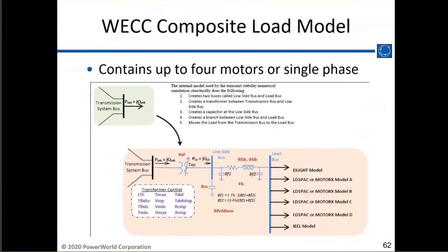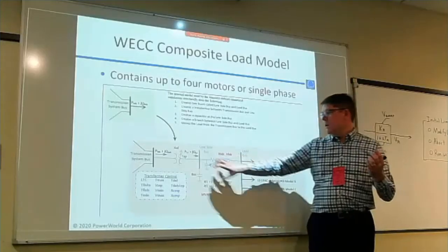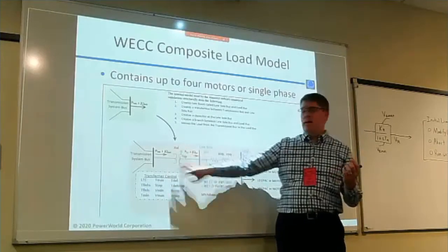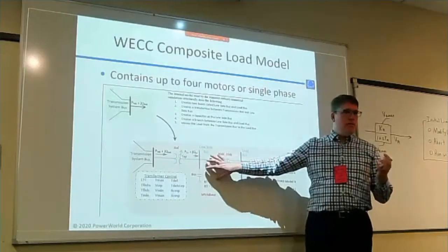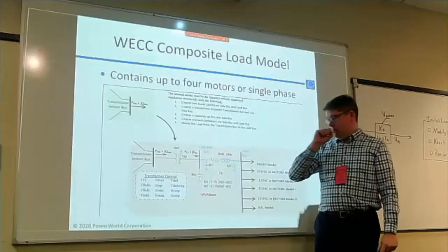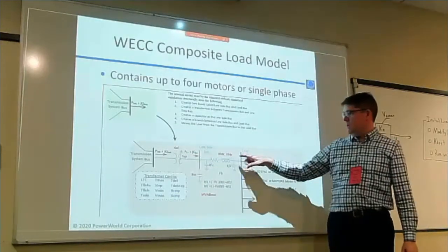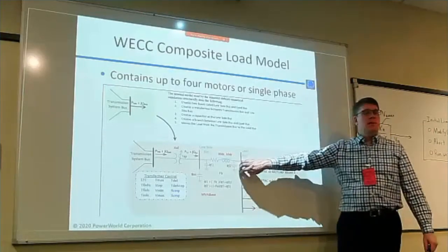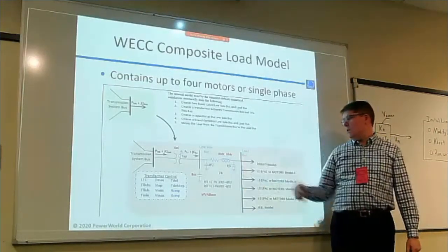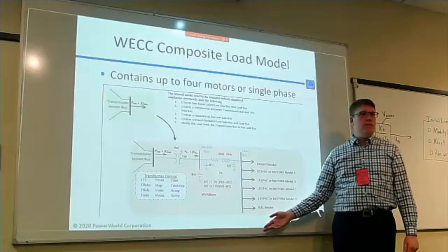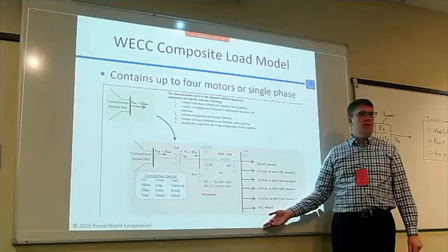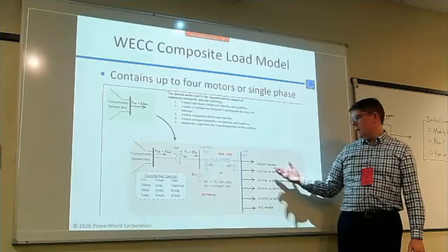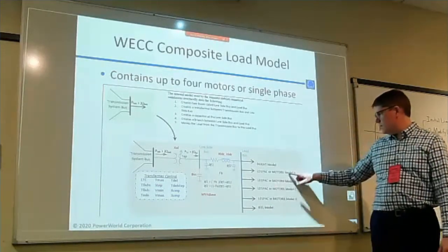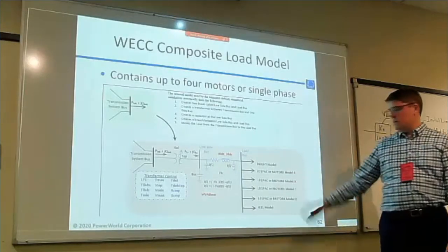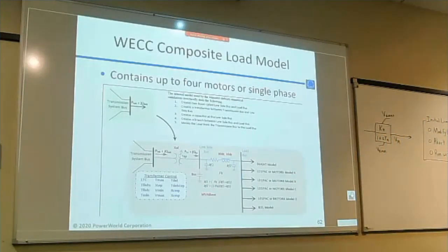So we're going to add 2 buses to your system. We're going to calculate the tap here. We're going to calculate the impedances here from the input data that's in that model. We're going to calculate what the P and Q that actually gets down to the end of this feeder is. And then we're going to chop that up into a bunch of pieces or components, thus composite components. And for your model, in practice you have 3 induction motors, 1 air conditioner model, a static model, and an electronic load model.